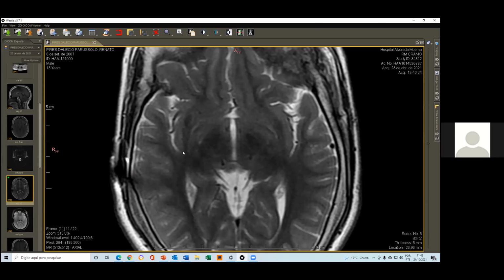Arthur, a couple of questions have been brought in. John Willie was asking, what kind of frame did you use? We use a frame called Micromar. The maker is a Brazilian company. It's definitely the most frequently used frame in Latin America. And do you know what the pin force is on that frame? Yeah, there is a manometer there, and we always use the manometer.